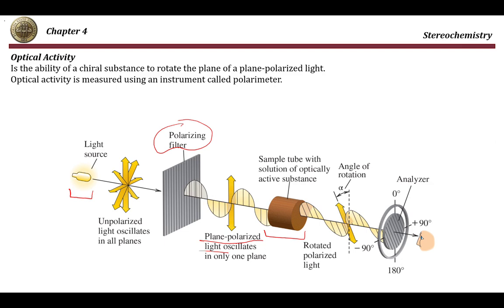When this light, called plane-polarized light, passes through a tube containing the sample you are testing, if this sample is optically active — meaning it is able to interact with light — it is going to cause a rotation of this light. Instead of moving undeviated, it will deviate by a certain angle alpha, either to the right or to the left, and at the analyzer or detector the angle of deviation is measured.